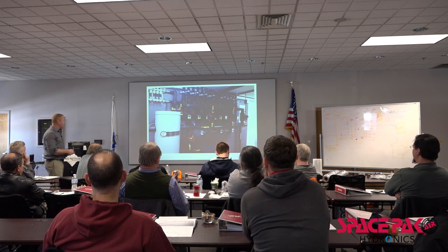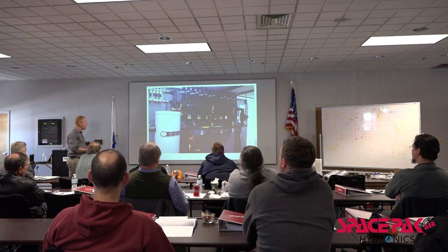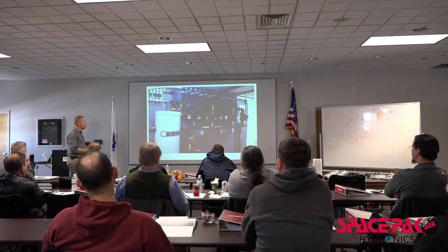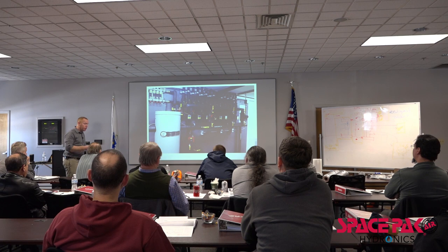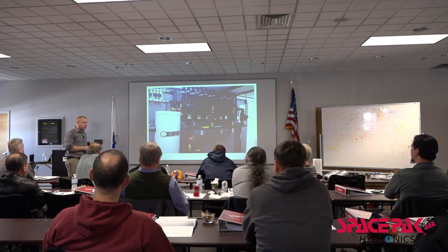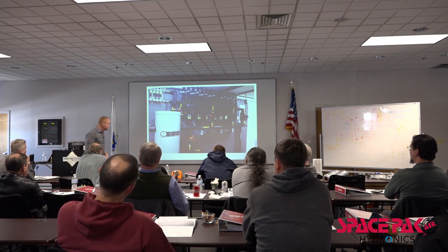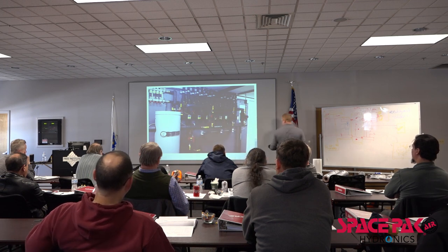Another project, and this is not our buffer tank. We only had buffer tanks start coming out a few years ago. This is a carbon steel buffer tank. But what do you notice in this chilled water application? Insulation. If we're going to do chilled water and we're going to insulate our pipes, we 100% absolutely need to insulate our pipes. And then we're going to look at it, and then go back and insulate some more. Now, this system looks like it's insulated, right? It is, what I'm reflecting.